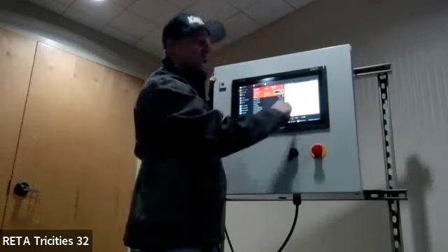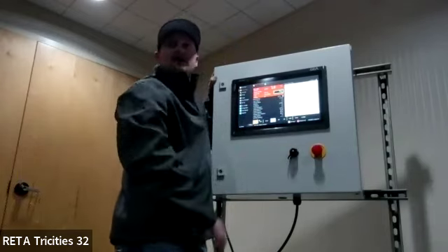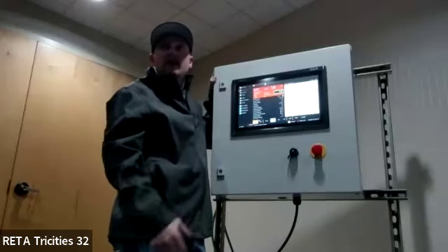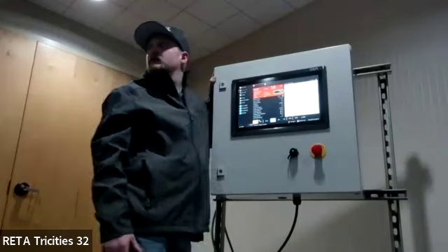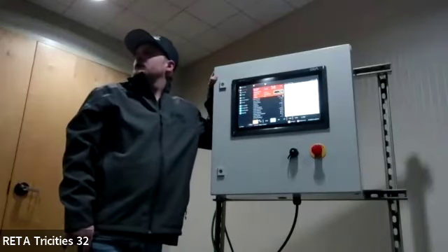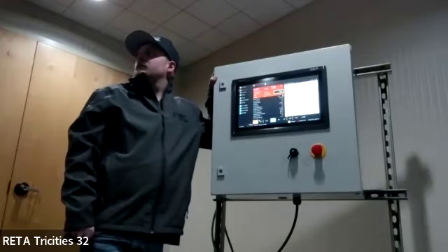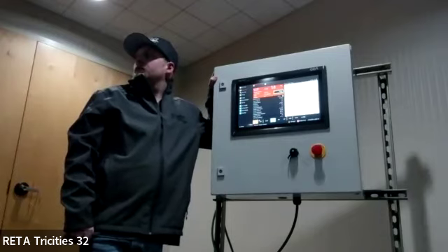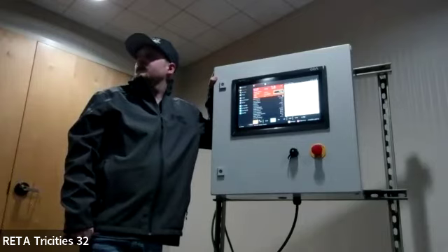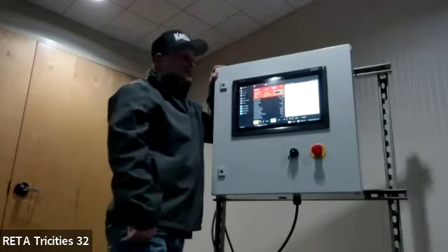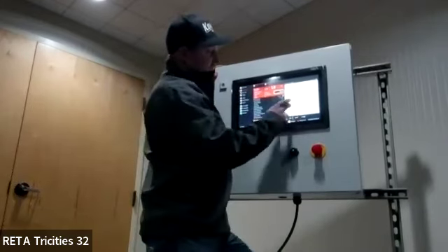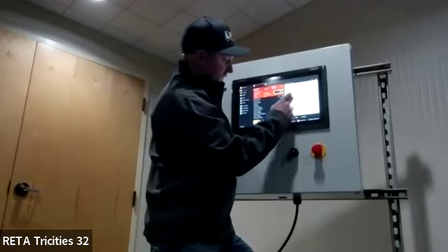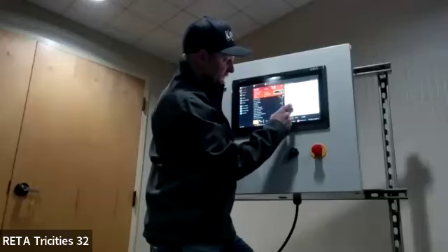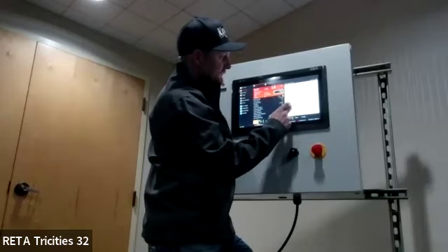You can do a circulation mode. You can enable that. It'll just kick the oil pump on every once in a while. You might be interested in that. This is if the plant is down for extended periods, we like to keep the bearings in the shaft seal wet. So you could set it up every 24 hours, it'll run for 10 minutes, or every 72 hours, it'll run for 10 minutes. That'll keep all the components wet and keep shaft seals lasting a little longer. Yeah, we're at a 6-week downtime right now. Yep, but we're at our facility, and this is something we should use. It's a great feature.